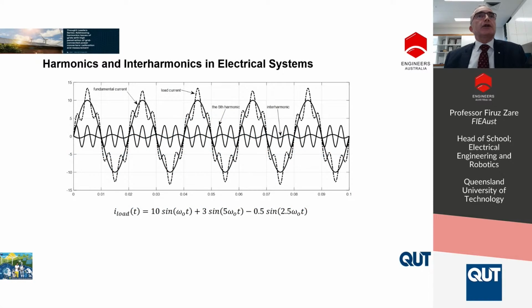Before I start the technical content of high-frequency harmonics in the network, I would like to explain definition of harmonics and interharmonics in power system. So if you look at this simple example, you can see that we have fundamental frequency, which is 50 Hertz or 60 Hertz, depending on the network. And in this specific case, we have harmonics, fifth harmonic, which is the integer number of the fundamental frequency. And we have interharmonic, which is non-integer frequency of the grid.